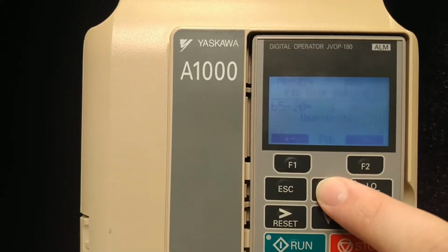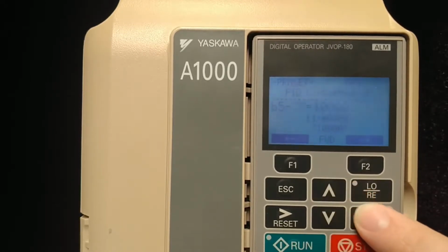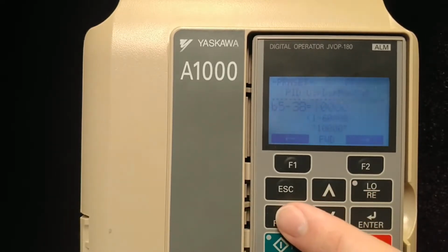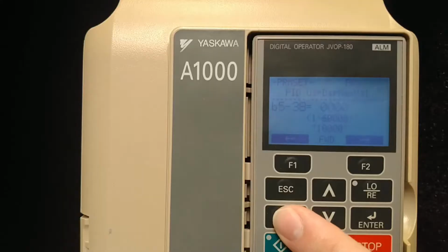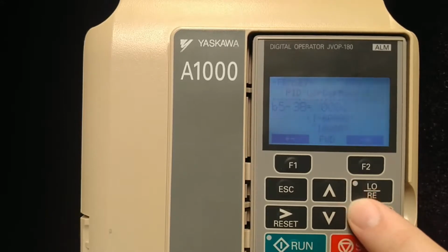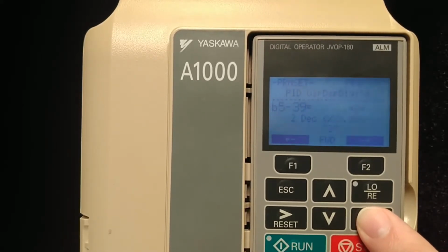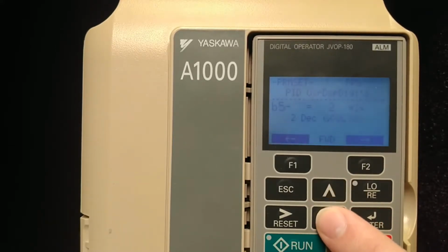The next parameter would be B538. This is the first parameter that we will set for the transducer range. Assuming we have a transducer that has a range of 0 to 100 psi, we can set B538 to 10,000, and B539, which is the amount of decimal places that we are going to be using in the B538 parameter set. If we set that to a 2, 10,000 with 2 decimal places is 100.00. So now our range is set up for a 0 to 100 psi range transducer.